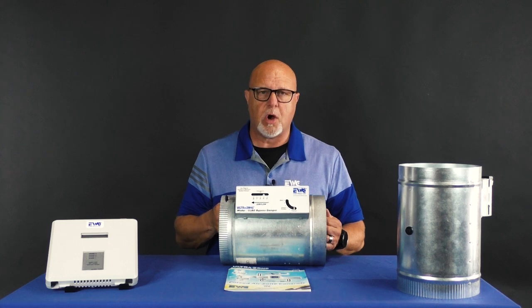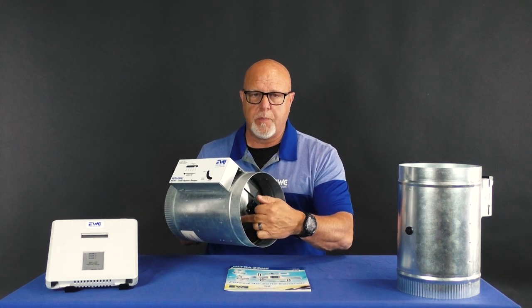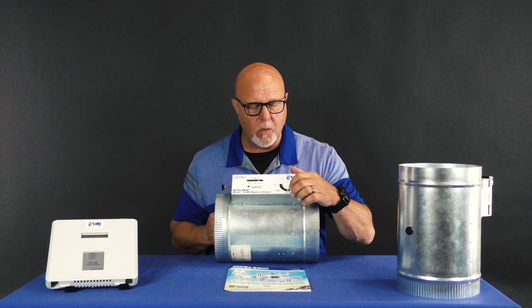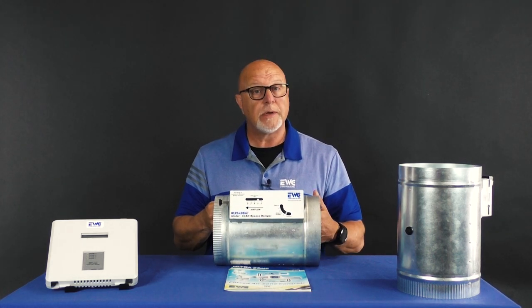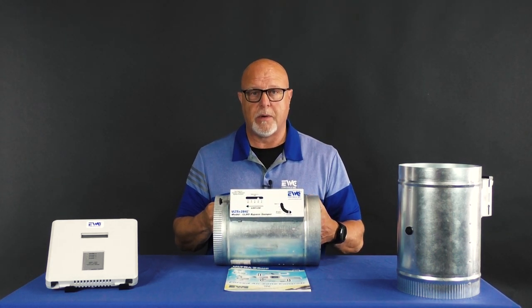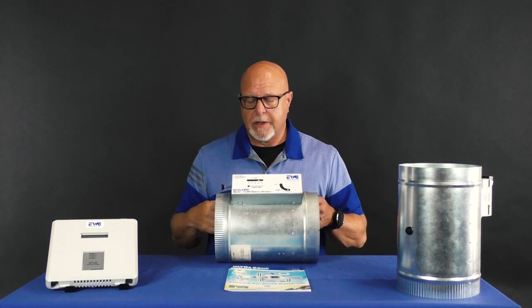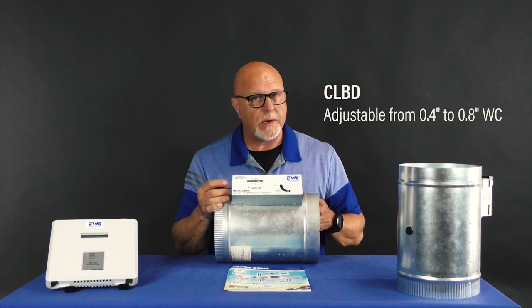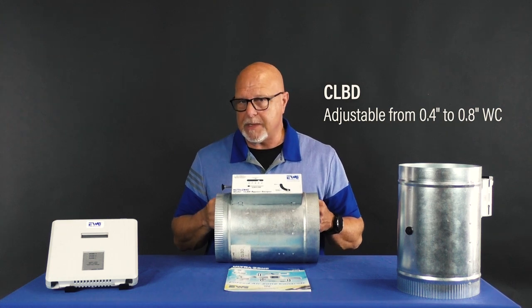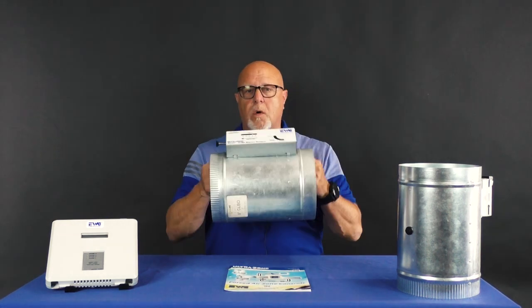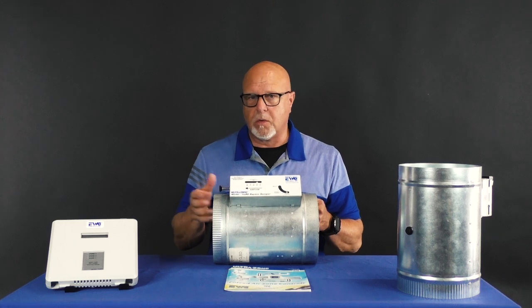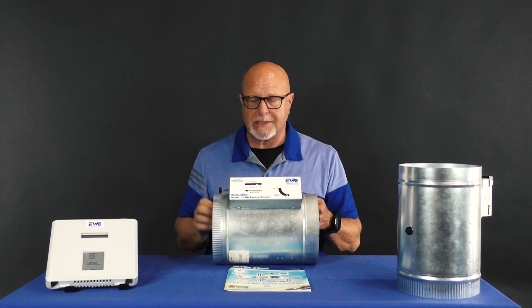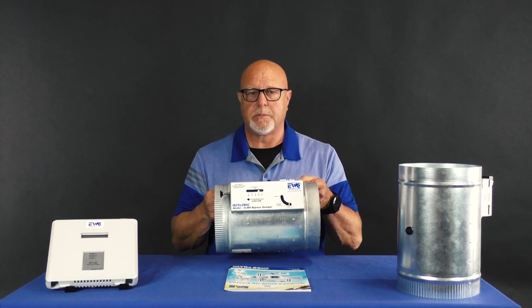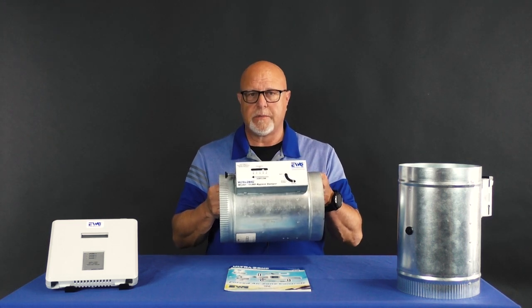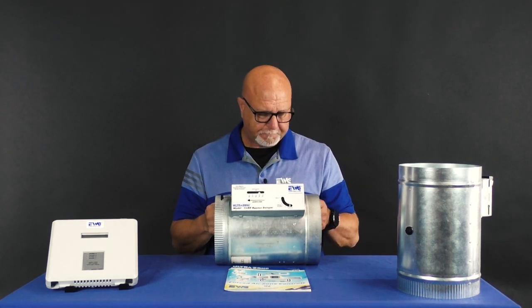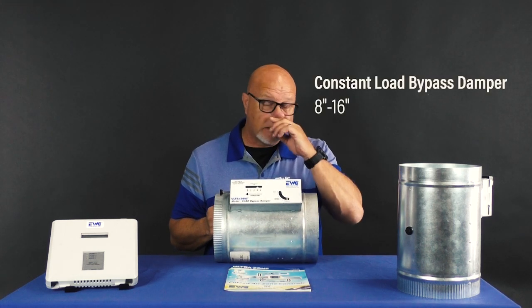I know it might be a little hard to see, but we've actually put a window on the front of the damper so you can see the blade of the damper operate when this is installed. This is adjustable from 0.4 to 0.8 inches of water column. It can be installed vertically or horizontally. Unlike the old weighted arm barometric bypass, where it had to be installed in a horizontal position, this gives you the freedom to install it both vertical or horizontal. We make this in sizes 8 through 16.